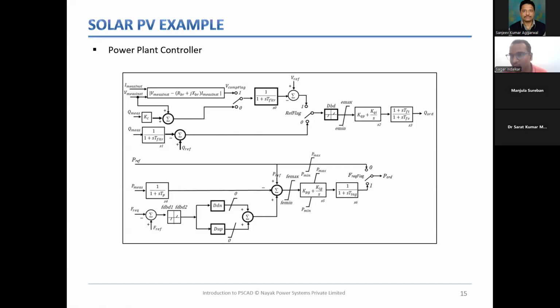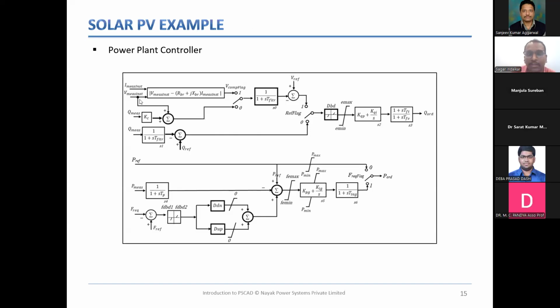It's very interesting to discuss the design of PPCs, but that may be a separate topic of discussion. To explain briefly, a PPC basically takes set points. Let's say this is your active power reference. It takes measurements. It passes the measurement through a filter. Then it takes out the error. That error is passed through a PI controller, and the PI controller basically takes action so that the error is minimized. Correspondingly, it will generate a certain P order, which will go to the converter. Similarly, the same philosophy is used for Q control as well, reactive power control.